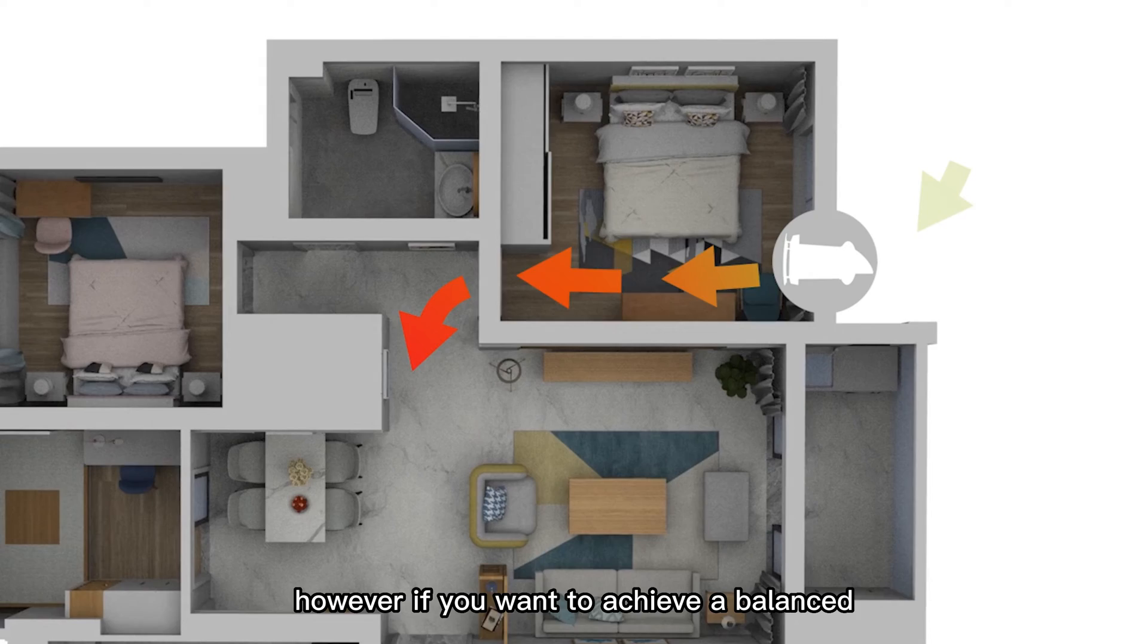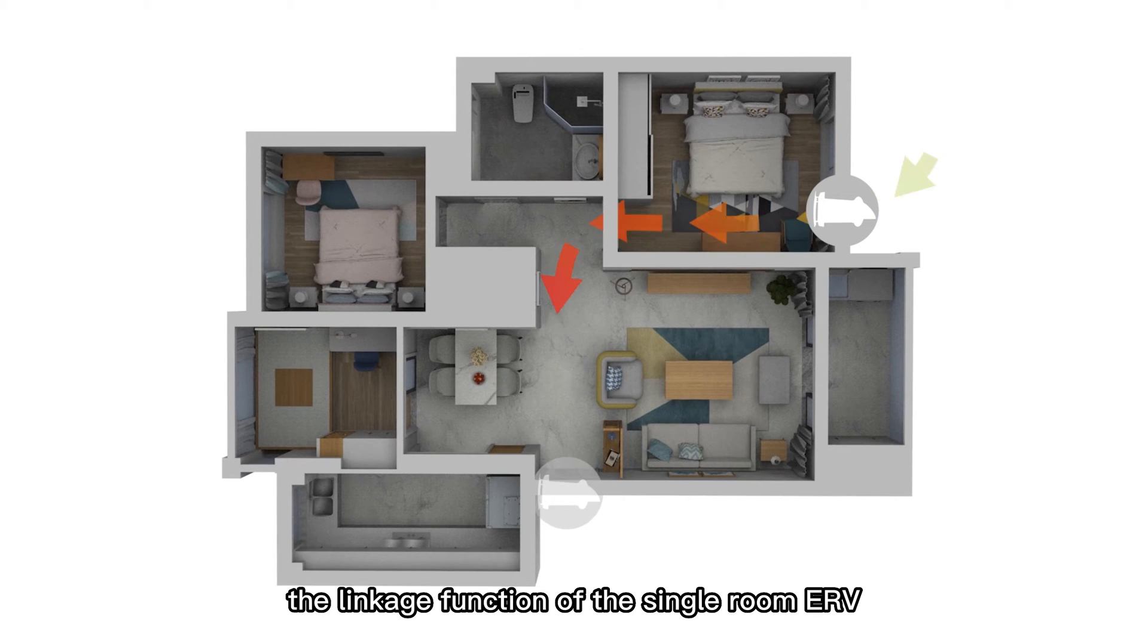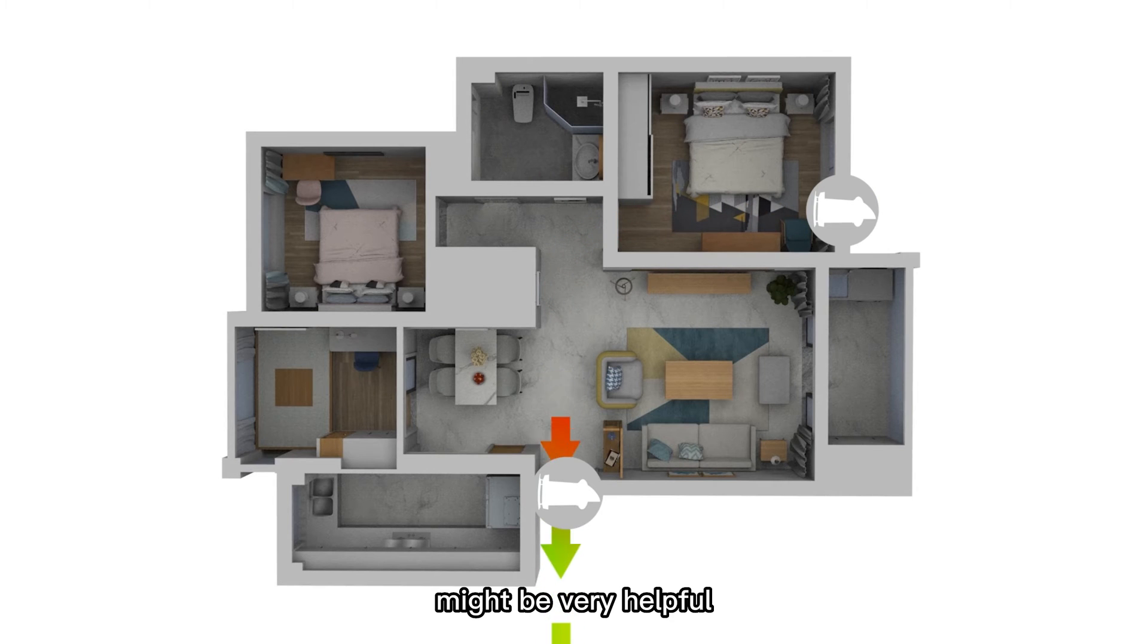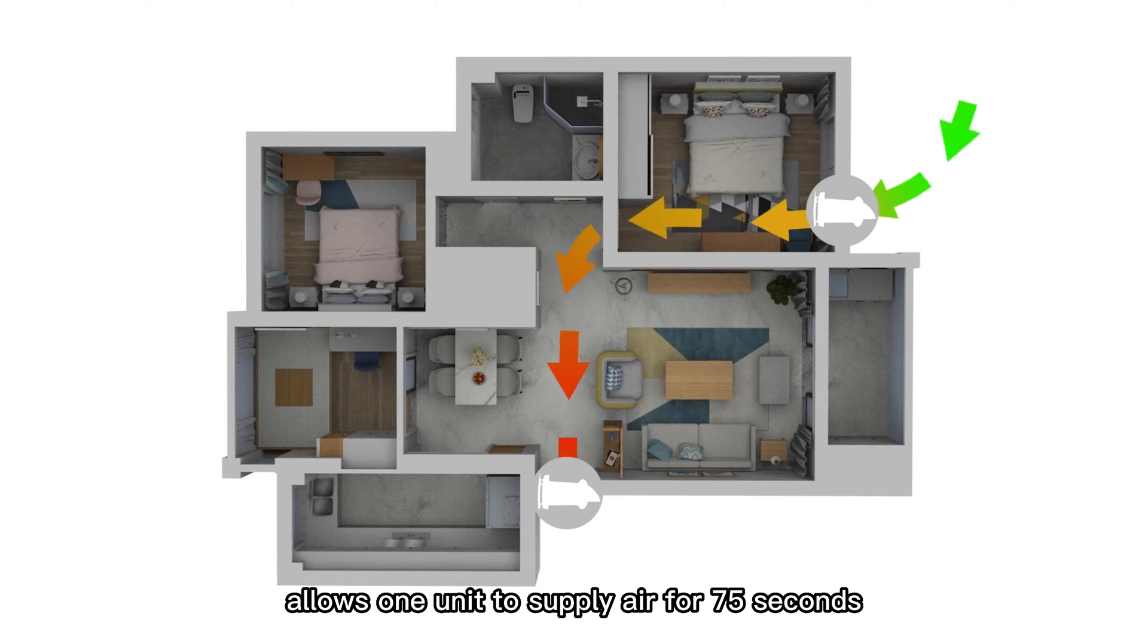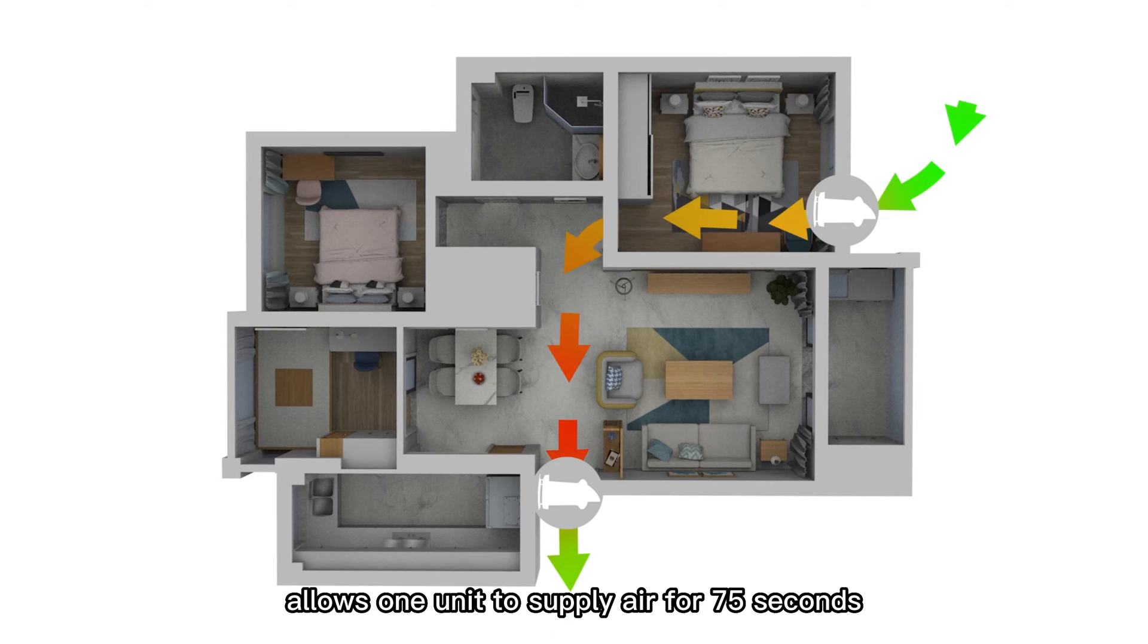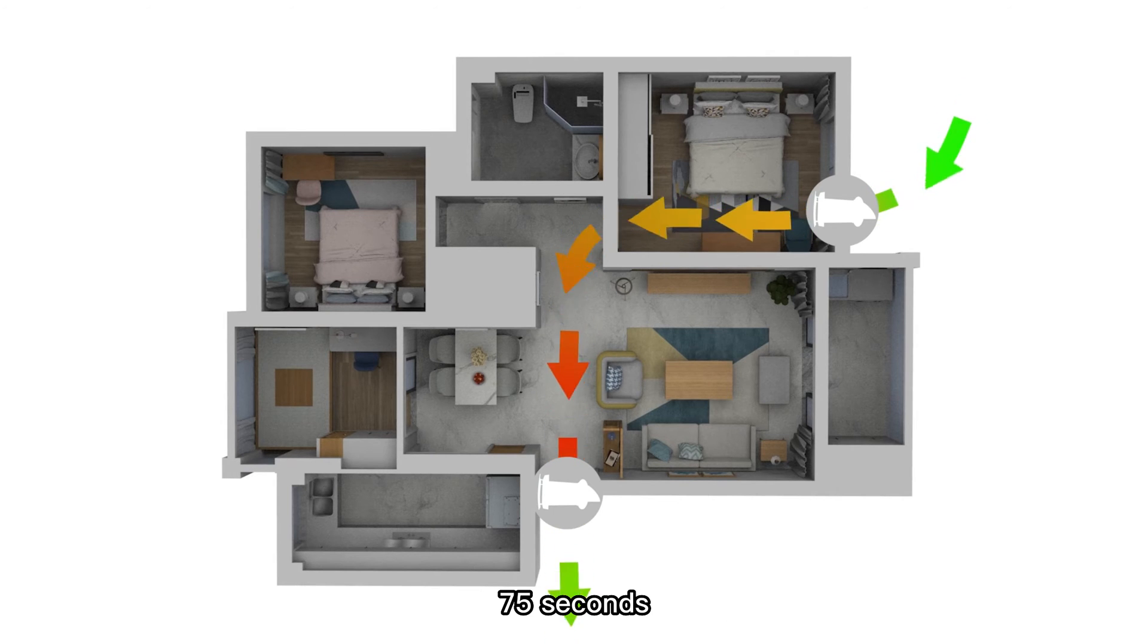However, if you want to achieve balanced ventilation by using such small units, the linkage function of this single room ERV might be very helpful. Installing two units allows one unit to supply air for 75 seconds while the other unit is extracting air for 75 seconds.